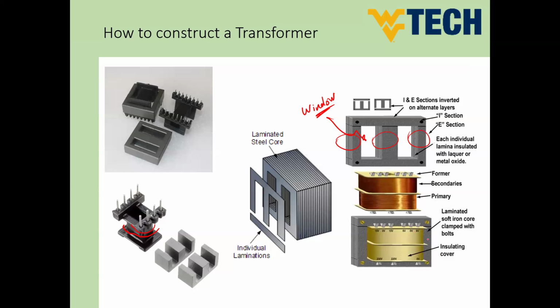Also take care, guys, that these windings are already insulated. The wire strand itself is covered by a material like varnish, for instance, in order to be insulated. Otherwise, if it is not insulated, all the windings will be shorted together. Okay, so the wire is insulated already. However, we still use another insulating cover by the end here in order to make a complete isolation.